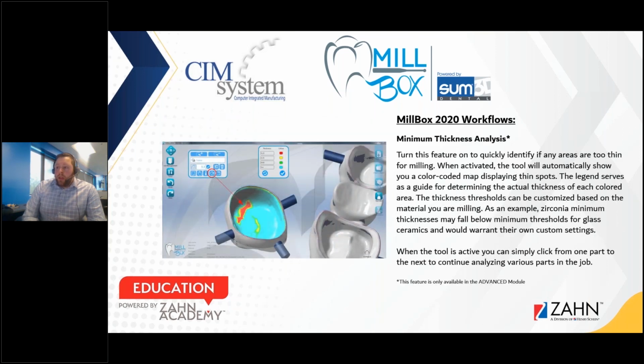The last thing that I wanted to touch on with Millbox 2020 is this new feature that allows us to use a thickness map while we're doing our milling process. The thickness map allows us to control the amount of thickness that we see on units and allows us to see if there are any units that are breaching the thickness that we might need in order to develop a successful crown.